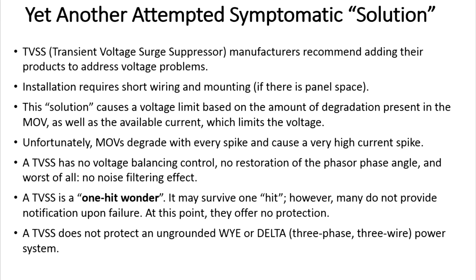Also, about half of the industrial and some commercial facilities, most chemical, virtually all offshore vessels run ungrounded power systems, either powered from an ungrounded Y generator or from delta transformers. An easy way to realize if you have that is if you have three-phase, three-wire, or a system without a neutral. TVSSs are not manufactured to protect those because they do not survive in that environment.